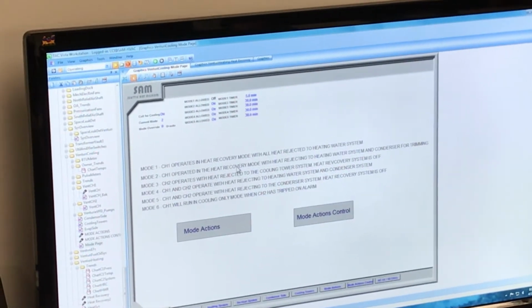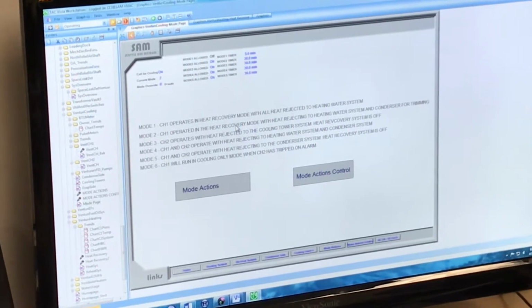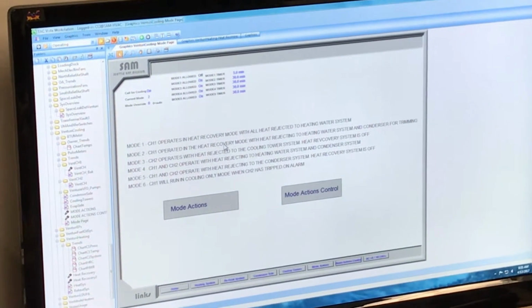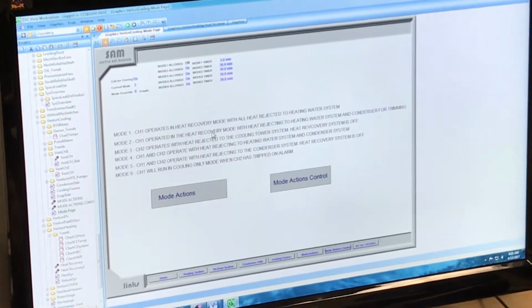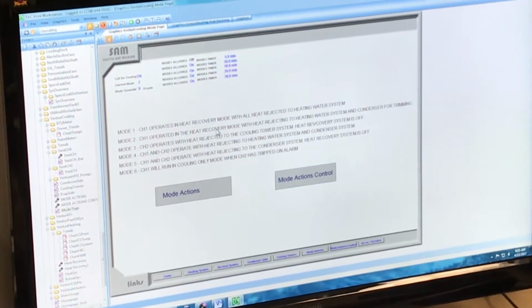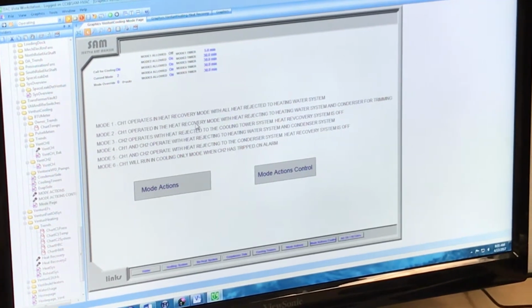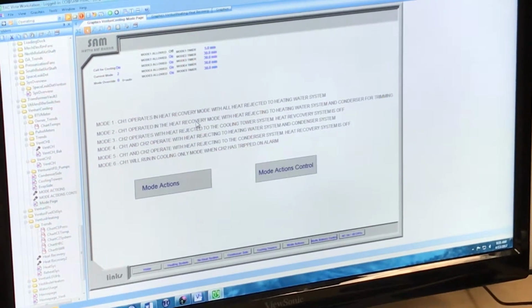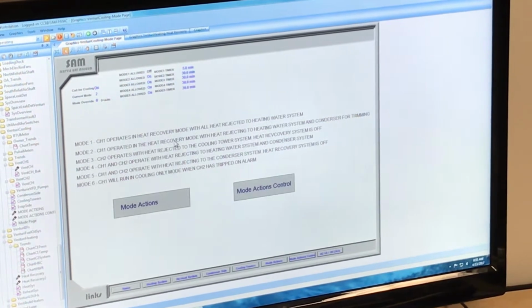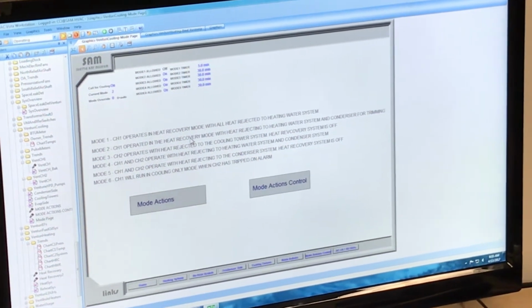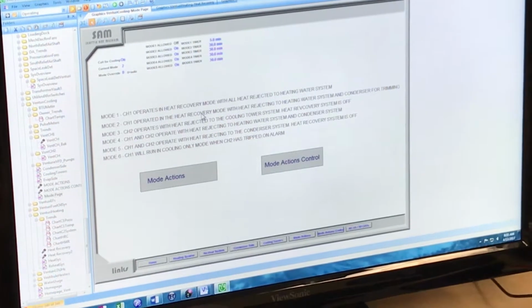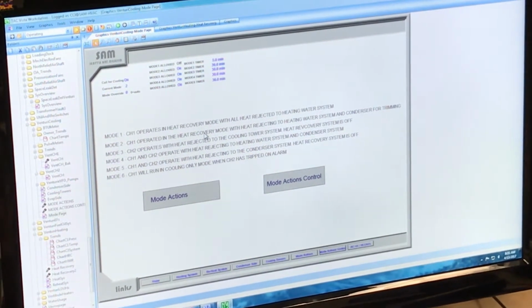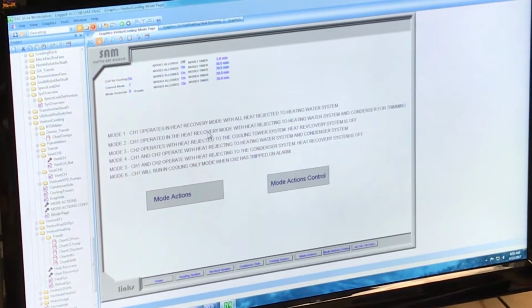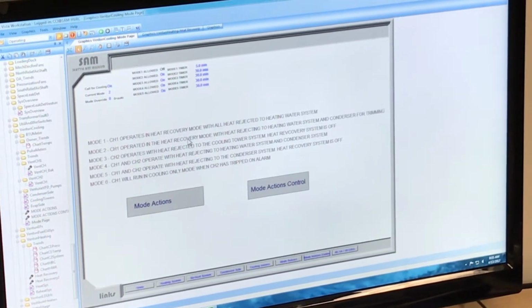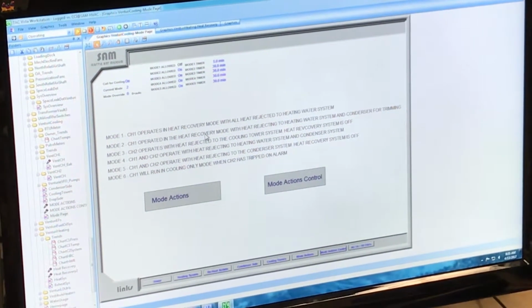So chiller at mode 2 means it covers the demand and also goes to the cooling tower. Yes. Heating, it covers the heating demand. It just doesn't want to get it too hot, so it trims it off. Yeah, so it might not necessarily make it to the reheat demands. You might have to still use a little steam, but it's going to preheat reheat water to a temperature. So this is your steam conservation. So in another sense, chiller mode 2 is basically for winter time, right? It uses it a lot. Yes. Right. Okay. You're going to get your best benefits during the winter.